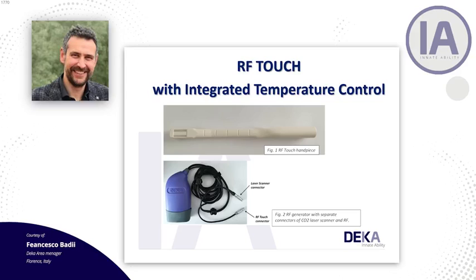For systems in the field, there is the possibility to order a specific kit that includes the new box, the software, and some RF probes. So what you have to change is just the software, replacing the TIS box here, because the existing one comes with only one wire, while you need two cables, and then the job is done.